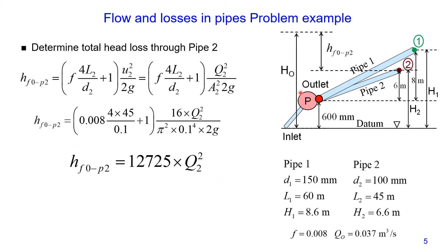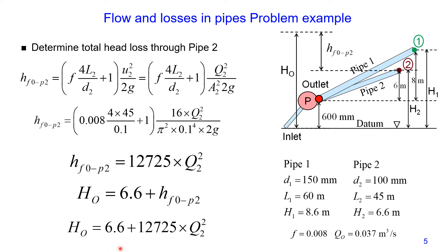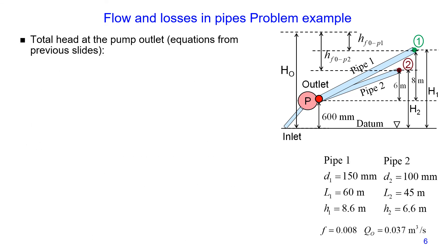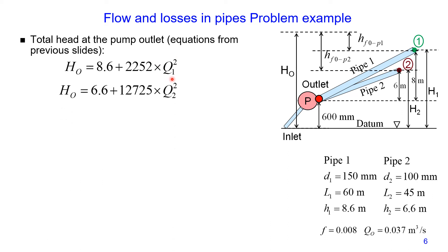From Bernoulli's equation, the total head at the outlet equals the total head at point number two plus all head losses along pipe number two. So we can express the total head at the outlet as: H_O = 6.6 + 12,725 × q2². We now have two expressions: H_O = 8.6 + 2252 × q1², and H_O = 6.6 + 12,725 × q2².